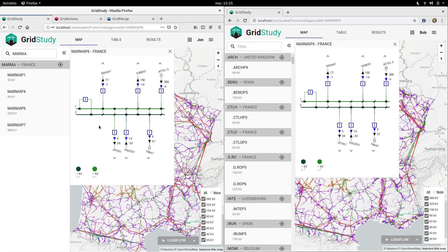To recompute all the electrical values, we need to run an electrical simulation. The simplest kind of electrical simulation is called a load flow simulation, and it computes the steady state of the voltage and power throughout the grid, based on the constraints of the power plants' production targets and the consumers' demand.